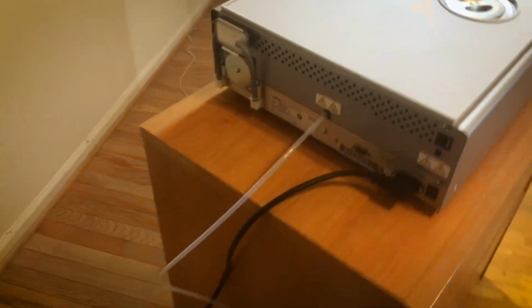It's technically not a portable autoclave, but it's portable enough because it only weighs 46 pounds. So from what we understand, it is the lightest autoclave that is out there and available for use. And of course, that's without water added, but we add that when we get there and we take it out. Another important factor about this autoclave is the cycle duration. Unwrapped instruments will cycle through the autoclave in approximately 6 minutes with 3.5 minutes of sterilization. If we get to the point where we might wrap some instruments towards the end of a trip, that increases to about 14 minutes total with 10 minutes of sterilization, but that might or might not be something we end up doing. In order to use the autoclave, a couple steps need to happen first.